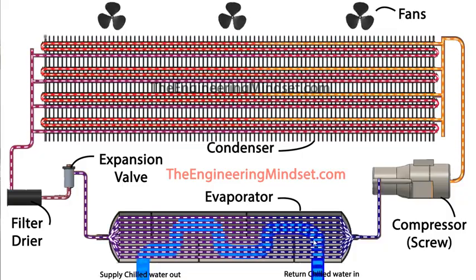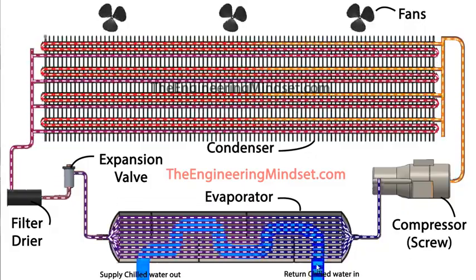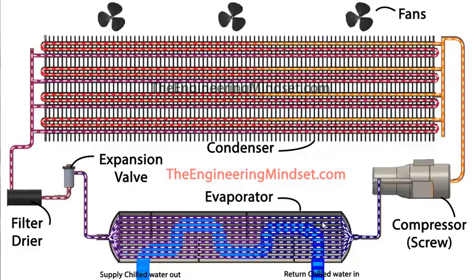So passing through the evaporator, we've got the chilled water coming in as the return water there, and then making its way through and out around the building to provide that air conditioning. It's absorbing the unwanted heat from the building and bringing that back to the evaporator, where it will exchange the heat with the refrigerant. So the refrigerant never leaves these tubes, it's always contained within them, and the water then passes around the outside of the tubes to absorb that thermal energy and take it away.